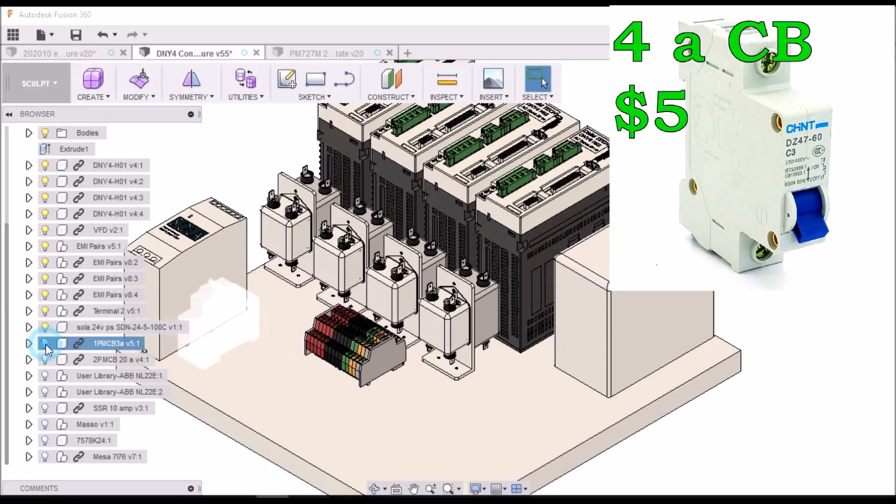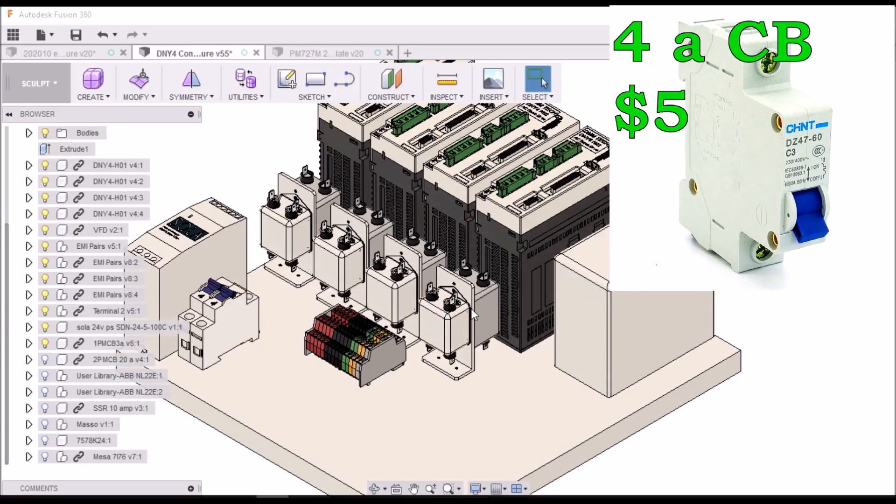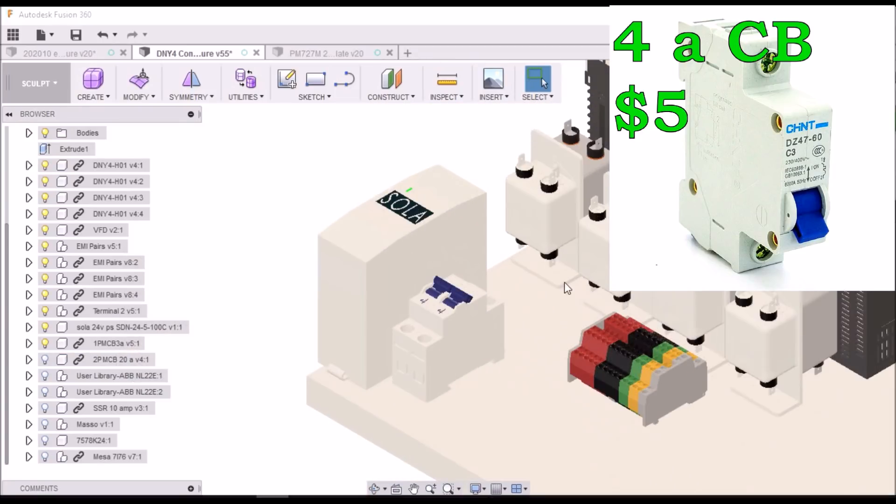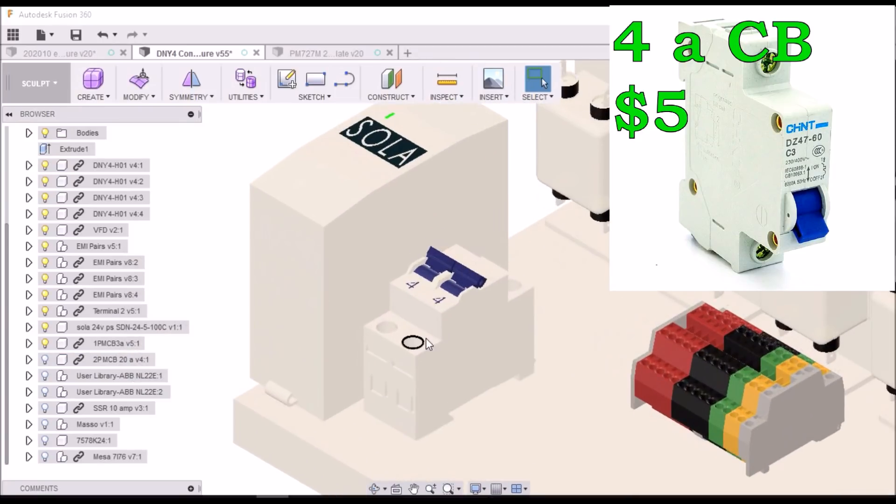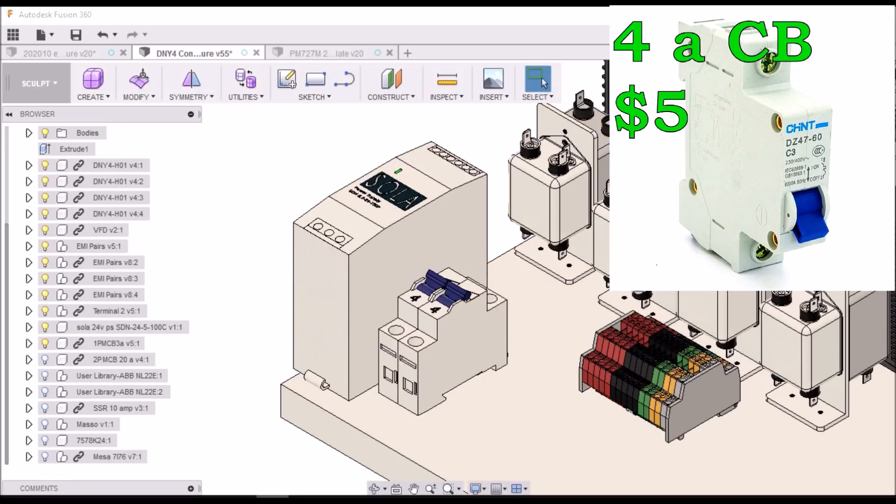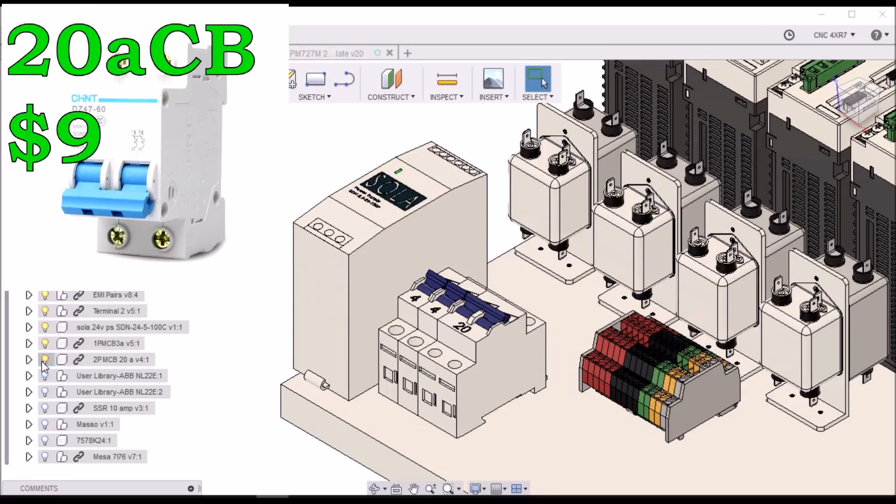I've picked up some circuit breakers. I need two 4 amp circuit breakers. It's 1 amp per drive for the control power. And then a 20 amp breaker for the VFD.